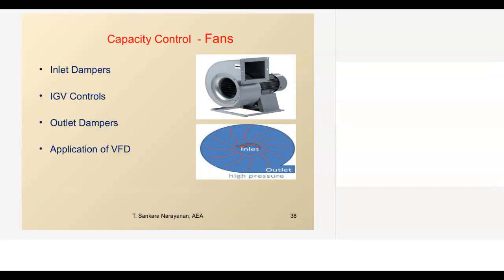Same, this is for fan control. Fan mostly, if you see, when you are having an inlet damper control, automatically we have saved maximum. Some of the large ID fans, we are having inlet guide vane controls. Wherever outlet dampers are there, we need to review what kind of energy loss is there. So both the inlet damper and IGV control will give maximum saving. Then the last stage is VFD application.